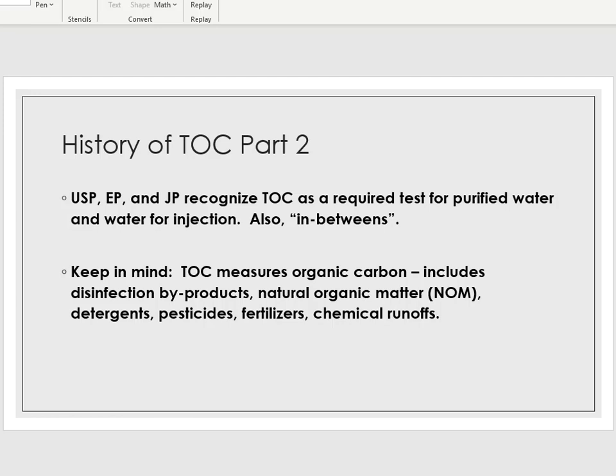So if there's a shot and somebody has to give you something, how can we ensure that those liquids are also pure? And all of the water that's used in the manufacturing line, how can we make sure that that is ultra pure as well? So the USP, the EP, the JP, they all recognize TOC as an approved instrument. We can get away with using it without a problem. So therefore, it made its kind of groundwork in the pharmaceutical industry as well as the environmental industry.